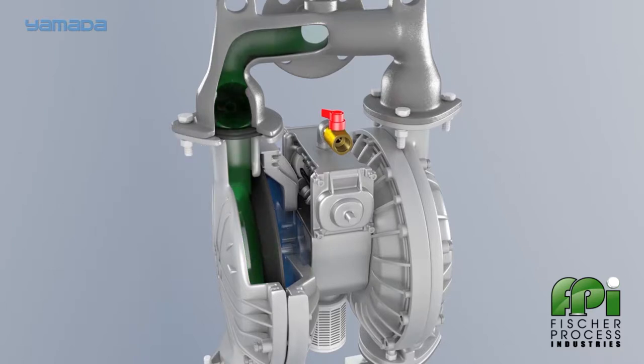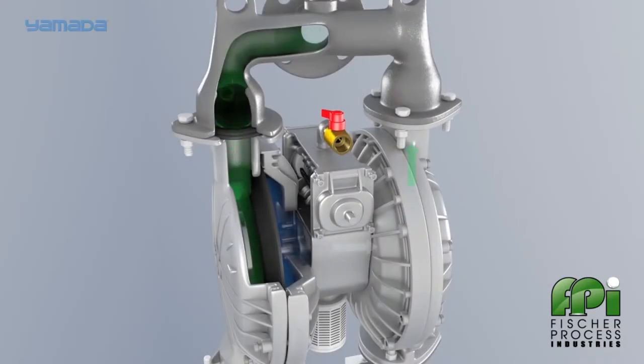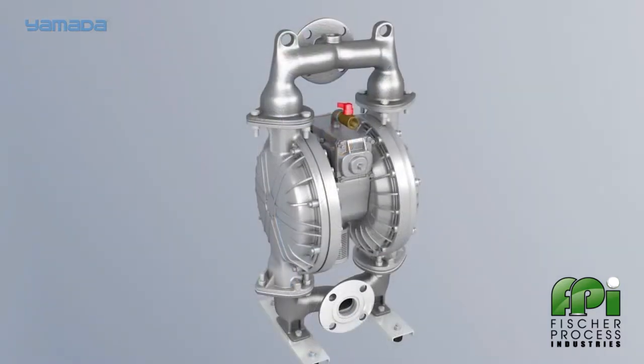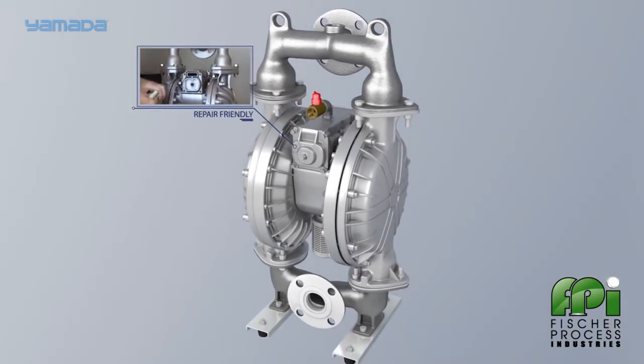The open port allows compressed air to exhaust from the back side of the air valve. The pressure drop produces a shift of the main air valve. This motion simply repeats on the other side. Our air valve is outside accessible for easy inspection and is completely repair friendly.